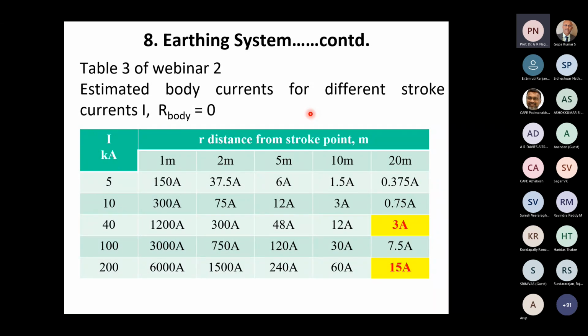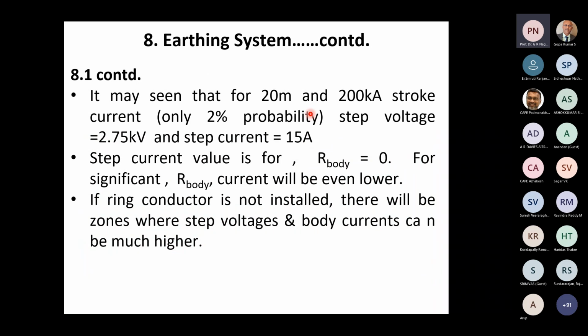So now we have covered the air terminal and then the down conductors and then the earthing system. As I told you, design of the air terminal system is the simplest because the principles are easy to understand. Down conductors, earthing system, the principle is even more easy, but extremely difficult to incorporate because there are many practical considerations which may come in the way of making it ideal. That is why we had to take recourse to the standards which are based on extremely, I'm using a double superlative, extremely extensive field experience. So we must follow the standards very closely in all these things. It's a question of human safety.